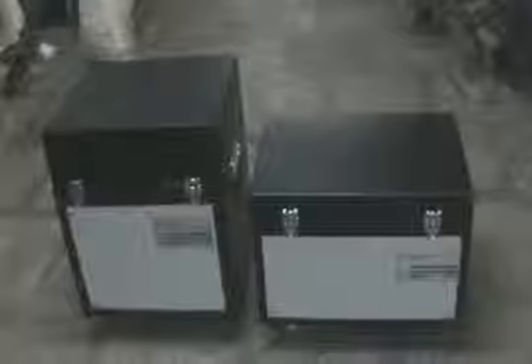The purpose of this video is to demonstrate to our viewers a high voltage test set. The rating of this test set is up to 30 kV and leakage current up to 30 mA. The high voltage produced by this test set is pulsating DC, meaning we have connected a diode at the output of the AC high voltage, which gives a DC pulsating output.